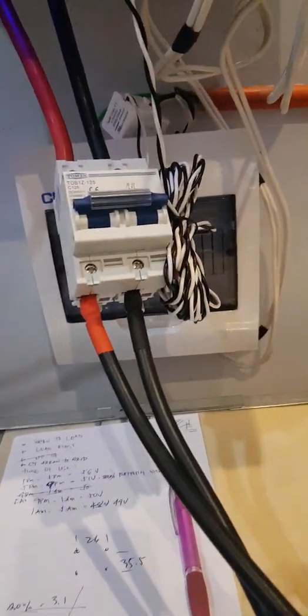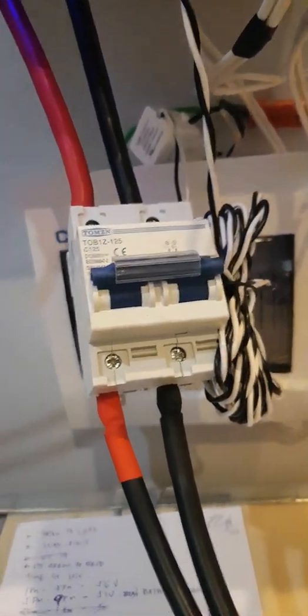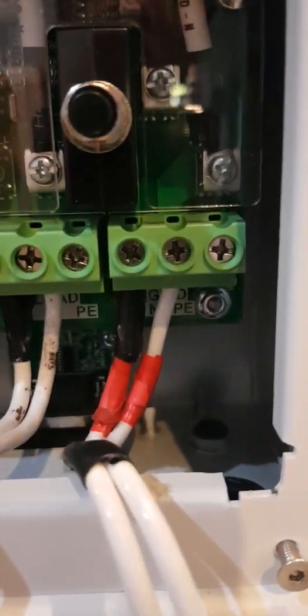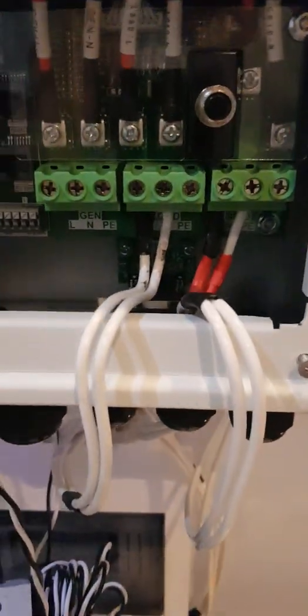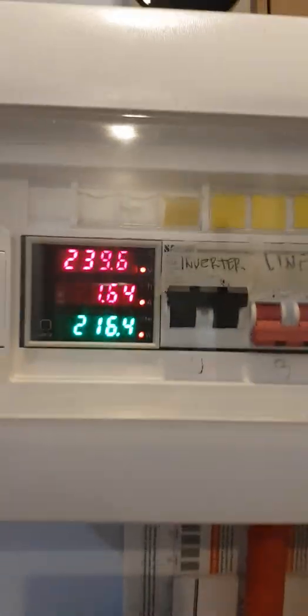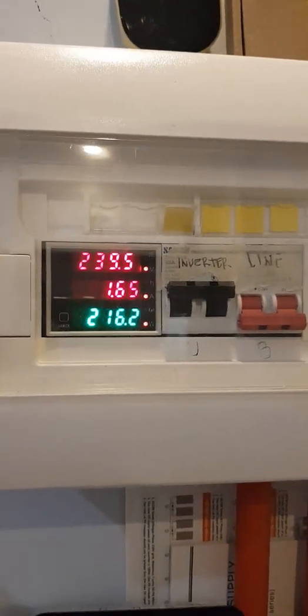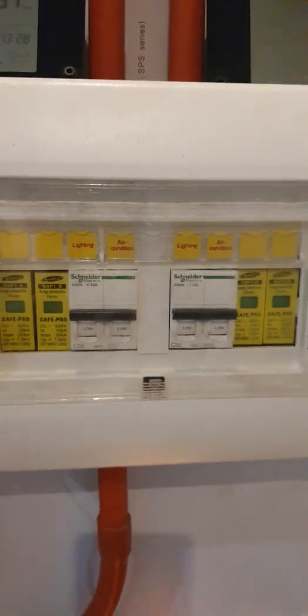both batteries. This is the circuit breaker for the battery. We have the circuit breakers also for the in and out of the inverter. So this is the actual connection. The right side is for the grid from your distribution unit or Meralco. The other side is the load, which is connected for your outlets or whatever connected device, connected appliances. So currently it runs through here. So this portion is the Meralco side, the in, and the other side is the output. So it is connected both with SPDs and also circuit breakers.